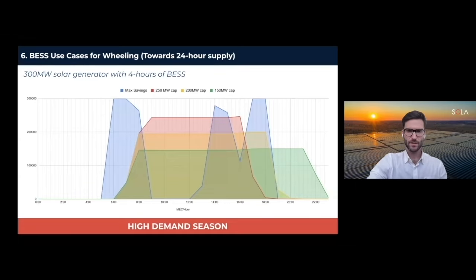And we've done a simple exercise of capping the generation capacity. So we can put out a maximum of 300 megawatts, but in each case, we use the battery to cap the generation capacity at these different thresholds. And what that does is it starts to squash that generation profile out, and it makes it flatter and cover more hours of the day.